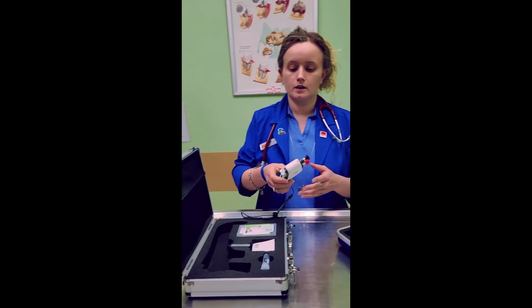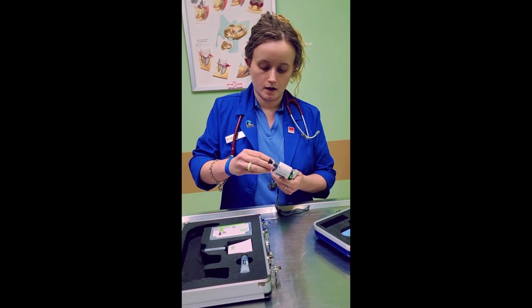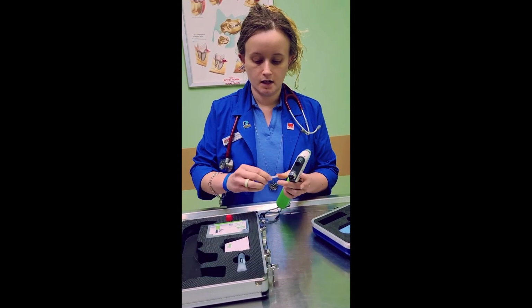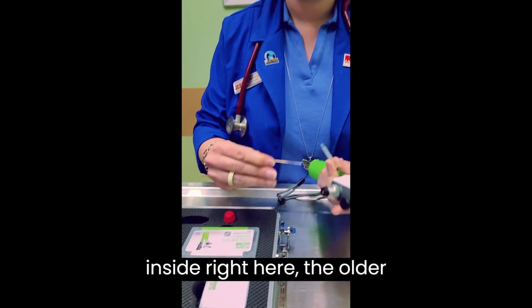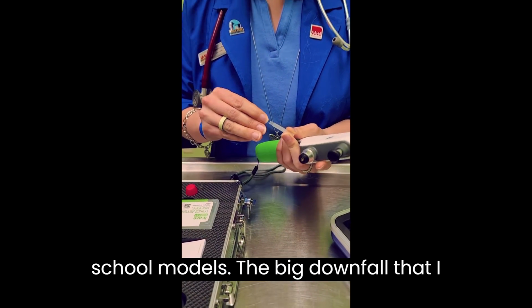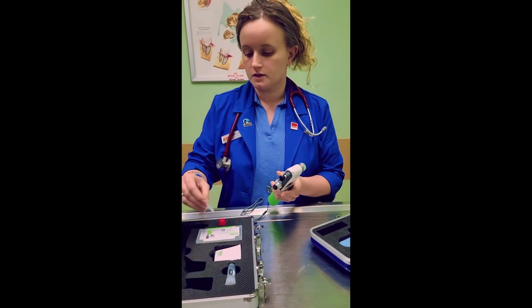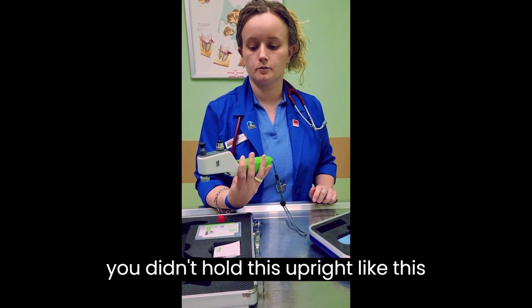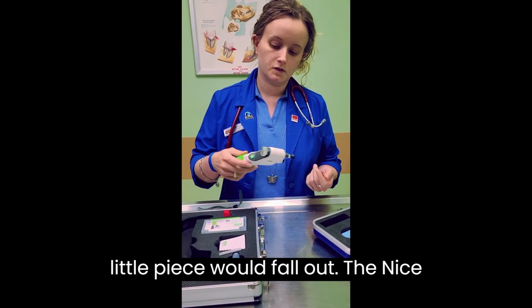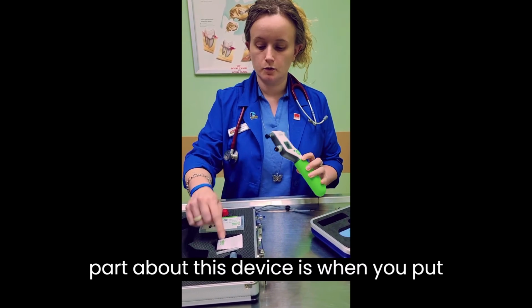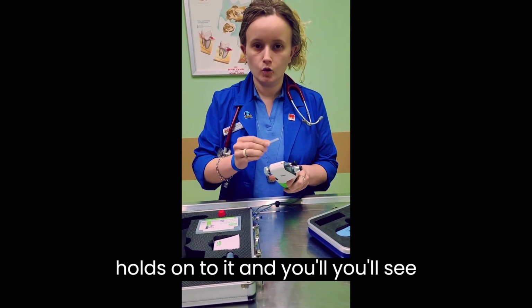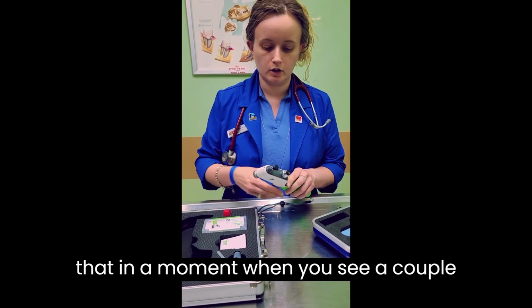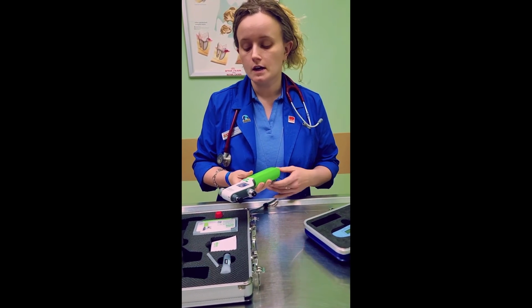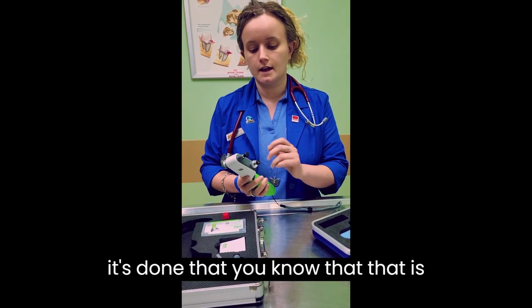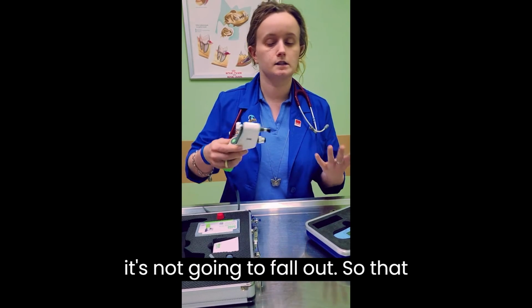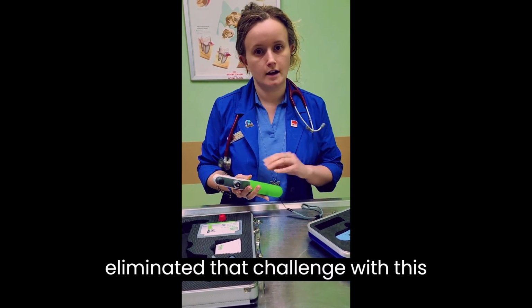The TONOVET Plus is a rebound tonometer, and it uses a little probe that goes inside right here. The older school models, the big downfall that I heard a lot of people complain about was the fact that when you put this in, if you didn't hold this upright like this or keep it pointed up in some way, that little piece would fall out. The nice part about this device is when you put this in, it grabs it and holds onto it, and you'll see that in a moment when you see a couple of videos of this device in use. But it does a little vibration, and once it's done that, you know that it is locked in place, and you can do this and it's not going to fall out. So that eliminated that challenge with this device.